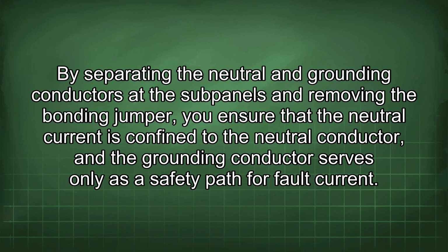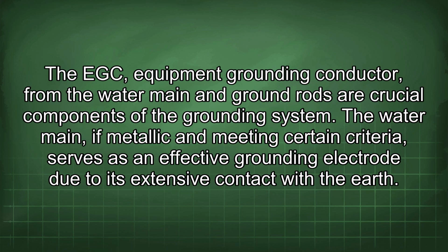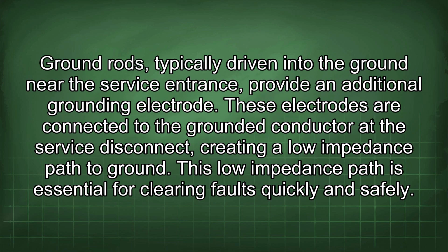The equipment grounding conductor, the water main and the ground rods are crucial components of the grounding system. The water main, if metallic and meeting certain criteria, serves as an effective grounding electrode due to its extensive contact with the earth. Ground rods, typically driven into the ground near the service entrance, provide an additional grounding electrode. These electrodes are connected to the grounded conductor at the service disconnect, creating a low impedance path to ground. This low impedance path is essential for clearing faults quickly and safely.